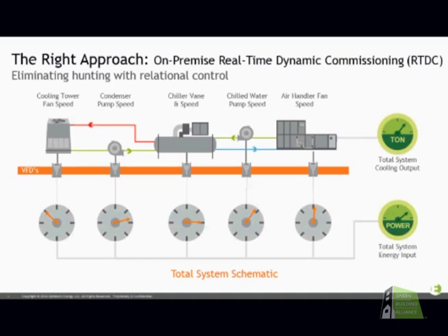The animated version. So again, in a typical system, if you're looking at maintaining a set point with each individual component, you're not really getting the most out of the entire system. Because, for example, that chill water pump is responding to those valve positions, and it's not looking at the entire system. So what we try to do is have everything working in concert together. So when you look at what the entire system is doing, you're able to operate it in such a way where you don't use as much power.